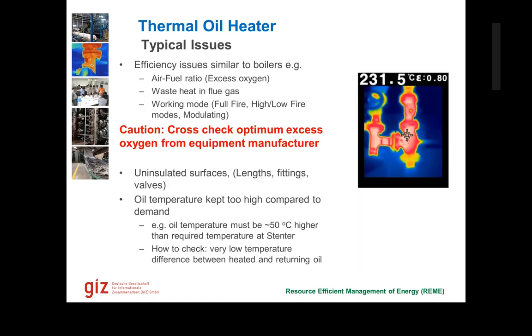So typical issues, same as steam when we talk about the network: uninsulated lines, air to fuel ratio, excess oxygen, working mode. Is it working at full fire, low fire, high fire? Is it modulating or not modulating? Usually they are not modulating, but they should modulate, not only between high fire and low fire, but also in between. So based on the temperature that is required in the process, they should modulate the thermal oil heaters. As I said earlier, if we need 200 degrees Celsius in the stenter, we need 250 degrees Celsius in the thermal oil.